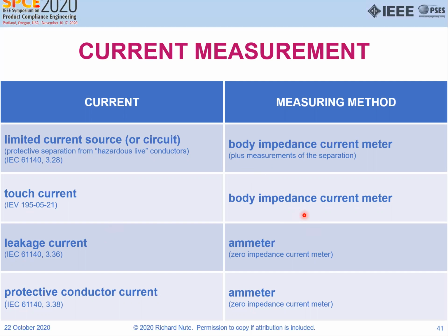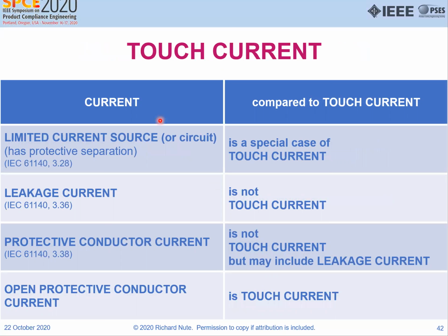Touch current is also measured with a body impedance current meter. Now the limited current source, you have to measure the separation characteristics also. Leakage current, if we follow the definition from 61140, you would measure it with an ammeter, a zero impedance current meter. Protective conductor current, because it's doing what it's supposed to be doing, you measure with an ammeter. Straightforward.